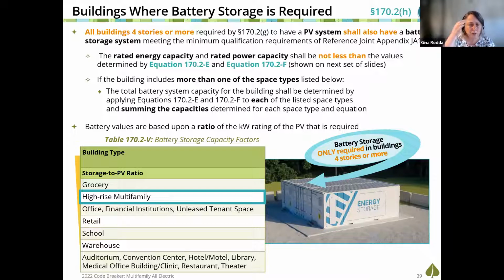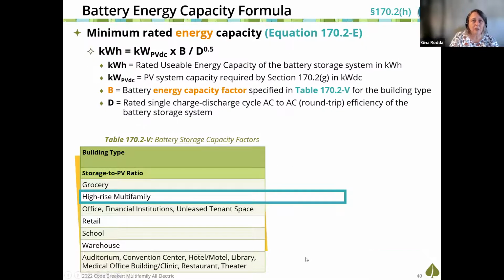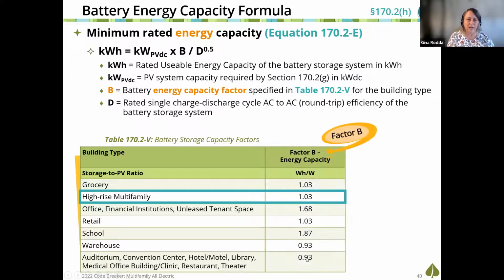And I look at 2 different measurements to determine my specification for the battery: the rated energy capacity and the power capacity. The energy capacity is the kWh supported by the battery. I take the PV kW, because I have to do PV first - battery is 100% dependent upon the PV kW that was dictated as needed for your building.